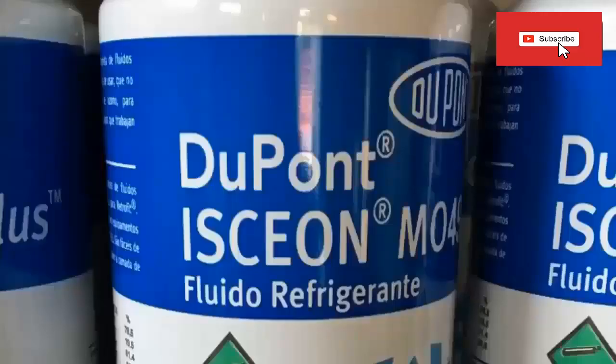Characteristics of MO49 refrigerant. 1. Do not use MO49 in units that use R22 or R404A refrigerant, since these gases work with very different pressures to obtain the same temperatures.